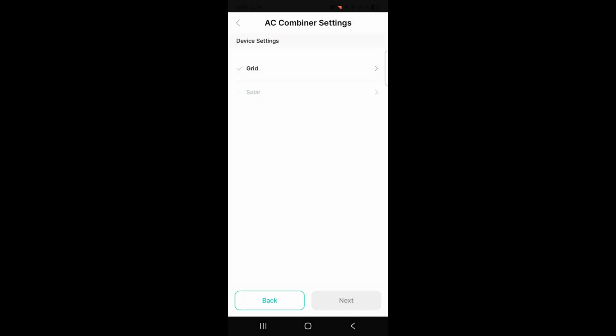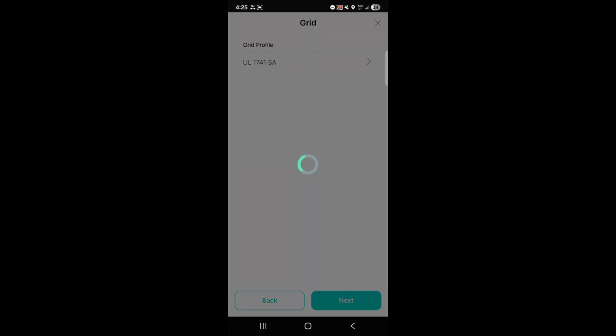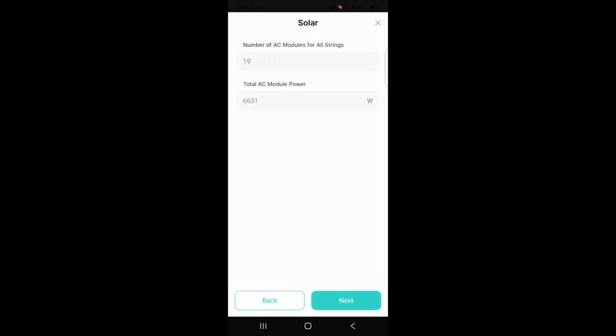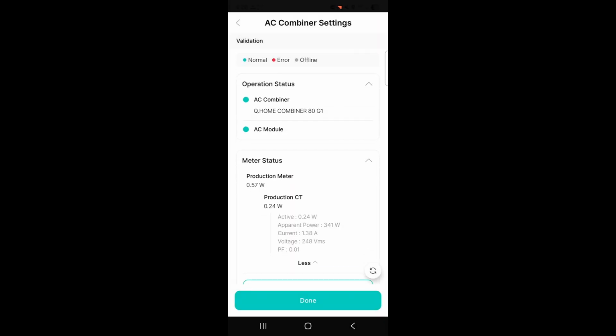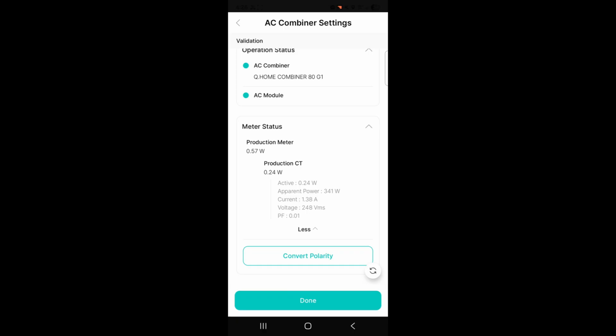We will enter the AC combiner settings now. Under Grid Settings, select the correct grid code. Under Solar Settings, the number of modules and total module power are automatically calculated. Verify the network status is live and the operation status is normal. If the operation status says error, you can check the error codes on this screen.